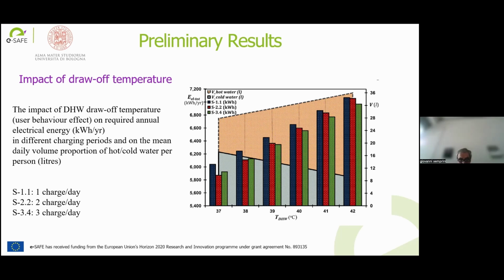And the rate of change in the energy consumption by variation of temperature is not the same for different scenarios. We consider 3 typical scenarios with 1 charge a day, 2 charges a day, or 3 charges a day. The normal trend is that if we increase the temperature of domestic hot water, the draw-off temperature, the energy consumption is greater, considering 1 charge a day.